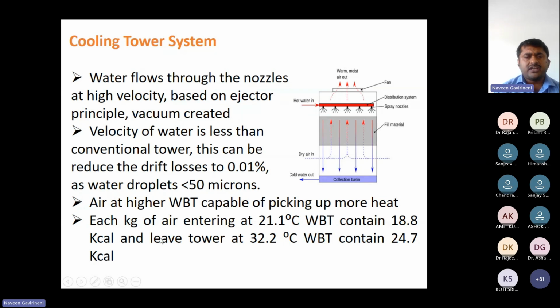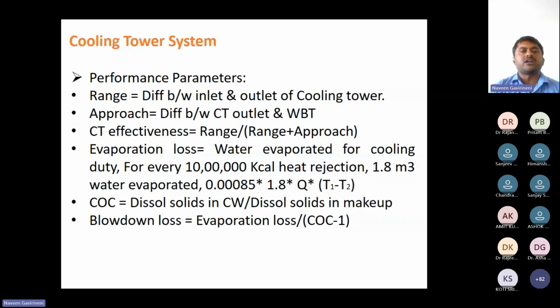Each kg of air entering at 21.1 degree wet bulb temperature contains 18.8 kilocalories, leaving at 32.2. As per design, they have given a 10 degree difference between inlet and outlet of the water. If we do not get that temperature, we are not getting the vacuum. While coming to the turbine part, I will explain vacuum and all those things clearly. So this is the cooling water system problem.